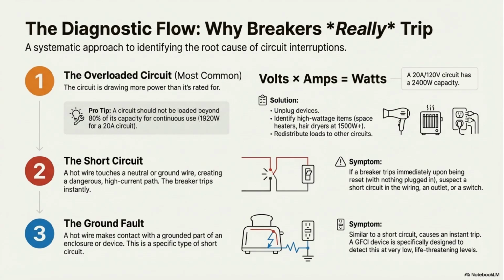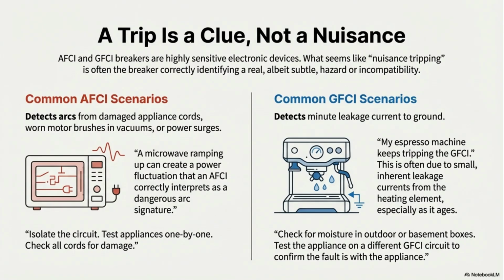The diagnostic flow for tripped breakers starts with the overloaded circuit, where the current draw exceeds the rating. Next is the short circuit, an instant, dangerous high-current path. Finally, the ground fault is a specific type of short circuit detected instantly at very low, life-threatening levels. A trip is a clue, not a nuisance. AFCI trips can be caused by arcs from damaged cords or motor brushes. GFCI trips often detect minute leakage current to the ground, possibly due to moisture or age, in appliances like espresso machines. In both cases, isolate and test the circuit or appliance.